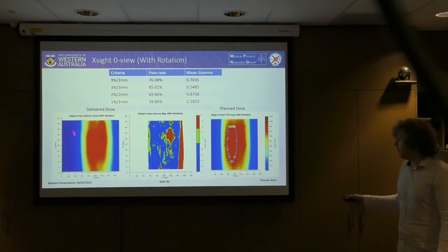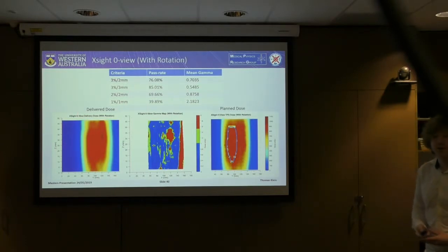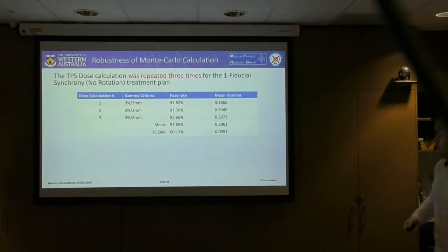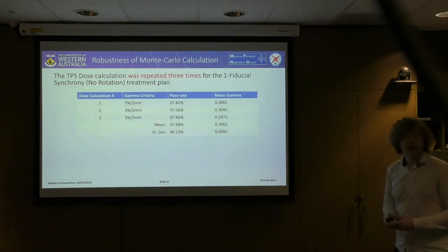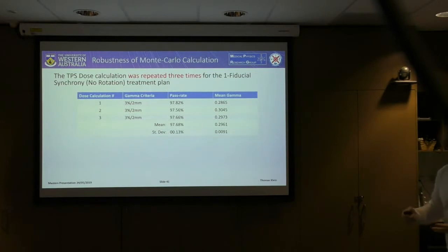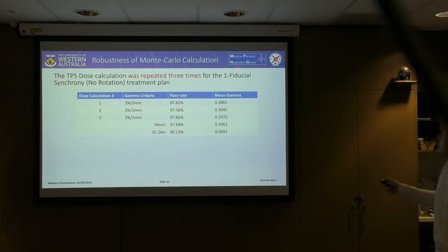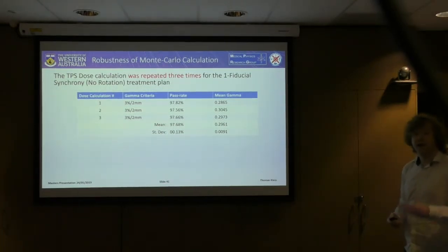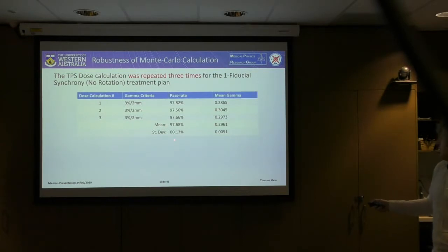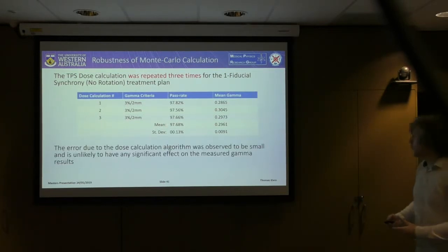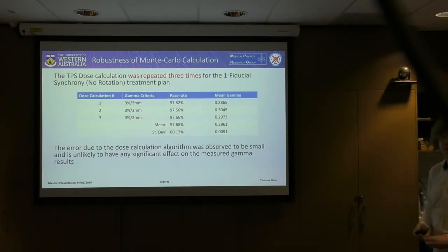This zero-view approach is how a moving target would be treated conventionally on a linear accelerator, showing how much larger the treatment area is by comparison. All dose calculations used Monte Carlo calculation, and we assessed the error in agreement attributable purely to variance in treatment planning dose calculation. Repeating the dose calculation three times for one treatment plan and comparing each to the delivery, the standard deviation was very small — so the error from the dose calculation algorithm is unlikely to influence any of our gamma results.